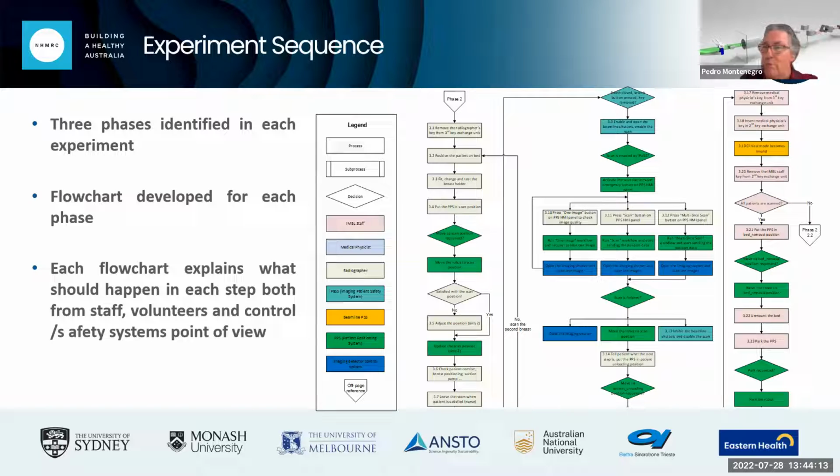Make sure all the rooms are closed on the way down the beamline, and then go to the satellite building, put that key into the key cache, and then turn it. And this will free a new key, which is the beamline staff key, which will remain in the pocket of the lead scientist preparing the beamline until the beamline is ready.